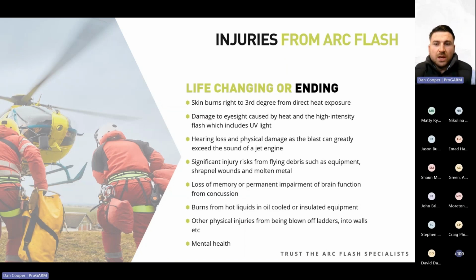I touched on droplets of molten metal as well, and this can cause skin penetration. With regards to hearing loss, an arc blast can cause around 140 decibels of noise up to 2 feet away, which can cause permanent hearing damage. So there are many significant impacts that can cause injuries to an individual within an arc flash.